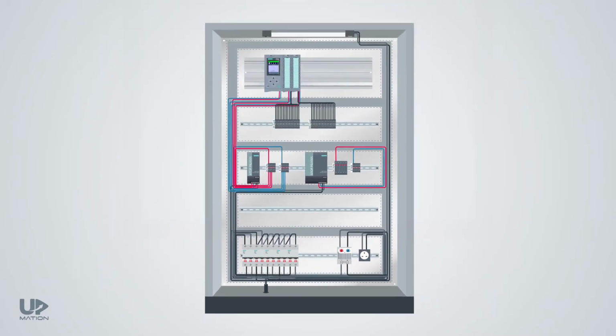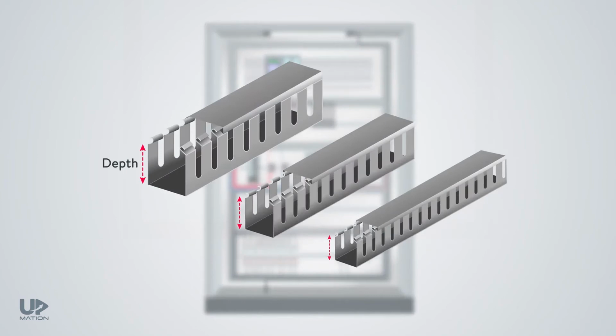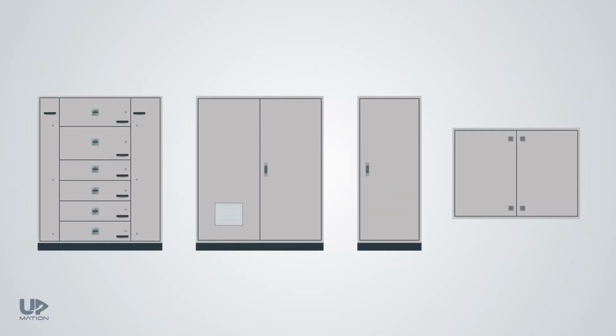As you see in this electrical control panel, in some routes we have more wires, and in some others we have fewer. So we should consider the depth and the width of every piece of wiring duct according to the volume of the wires we're going to lay into them. It is not only about the size of the wiring ducts, but the dimensions of the enclosure also have a significant impact on the comfort of wiring and installation of the electrical components inside the panel.